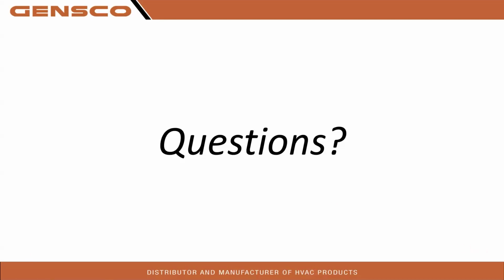Are you able to hear me? Yes, sir. Any functionality that you get or don't get just by using the Mitsubishi thermostat versus a conventional one? Yeah, so functionality wise, you're going to end up losing dry mode, which most people don't use anyways, for a little bit of dehumidification. The other thing you're going to lose is the ability to see any error codes on the system, which is always a big bummer, and also full communication with the heat pump.